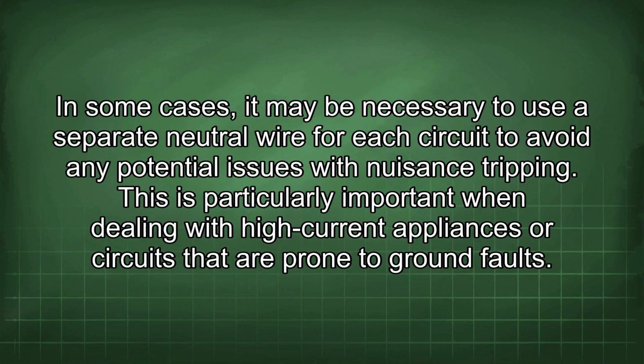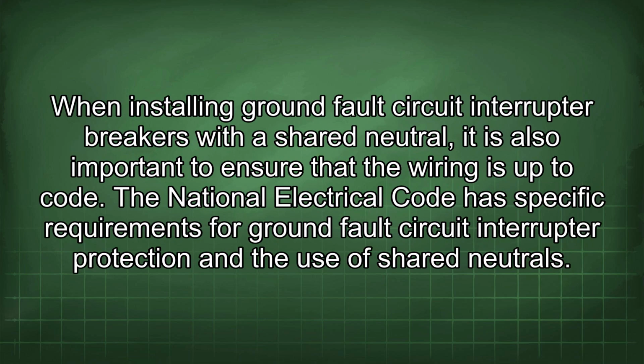In some cases, it may be necessary to use a separate neutral wire for each circuit to avoid any potential issues with nuisance tripping. This is particularly important when dealing with high current appliances or circuits that are prone to ground faults. When installing ground fault circuit interrupter breakers with a shared neutral, it is also important to ensure that the wiring is up to code.